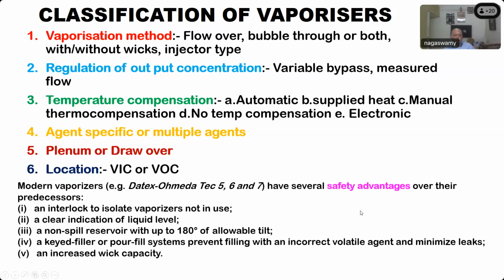And the features, safety advantages of the vaporizers: there is an interlocking system at the back bar, so you can use only one vaporizer at a time. There is a clear indication of the liquid level. What is that glass through which you see the level of volatile agent inside the vaporizer? What is that portion called?